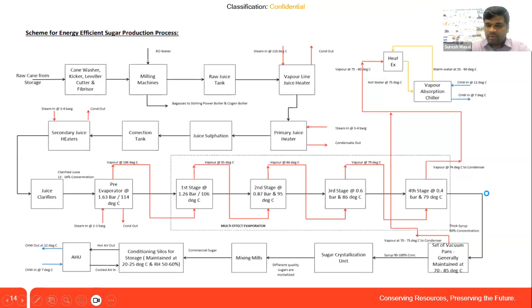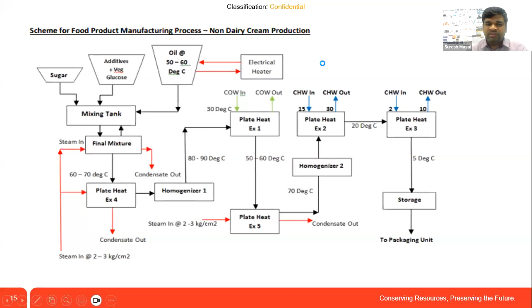This is a non-dairy cream production. In this also, any waste heat can be used to drive the chiller. Here normally 80 to 90 degree heat is given to the heat exchanger, and with the help of cooling water, that heat is rejected in the cooling tower. That heat we can give to the chiller, and the output from the chiller can be used for cooling and heating applications.